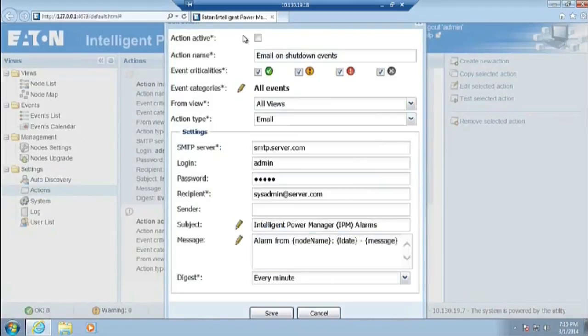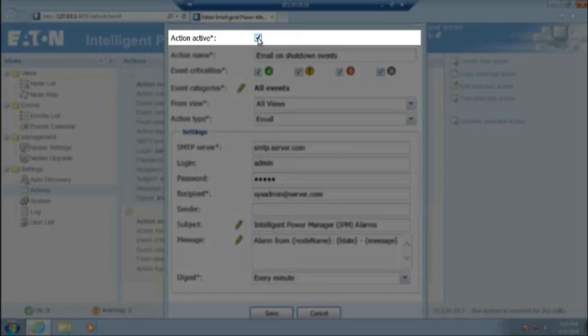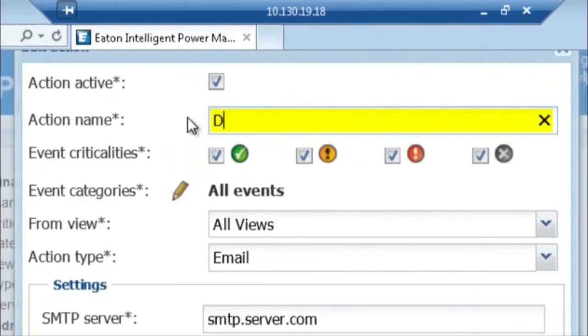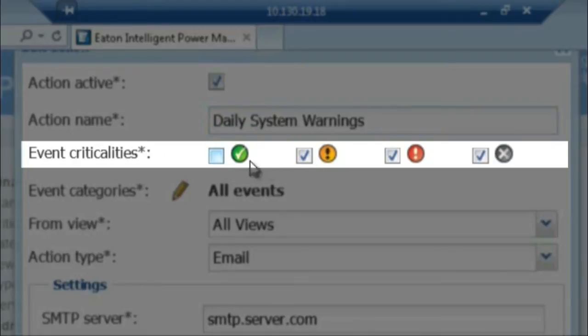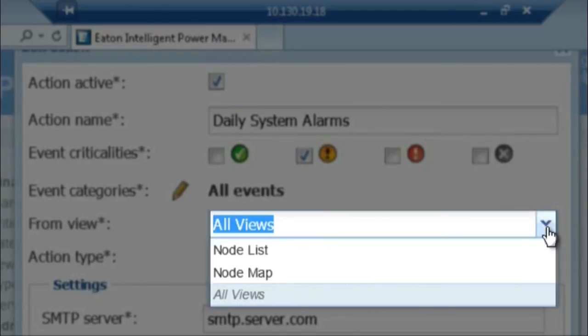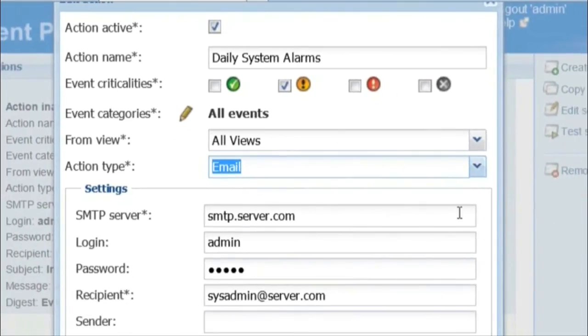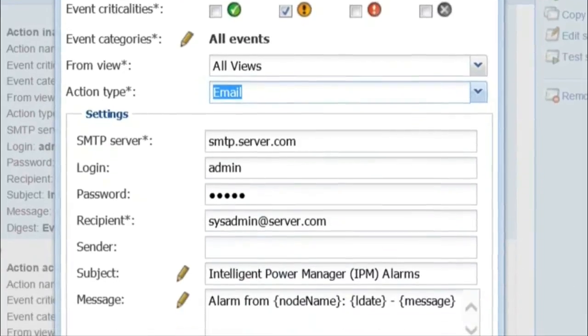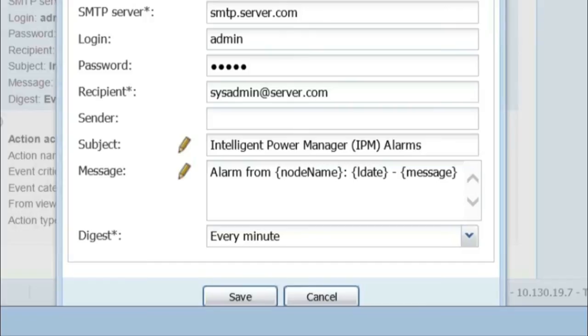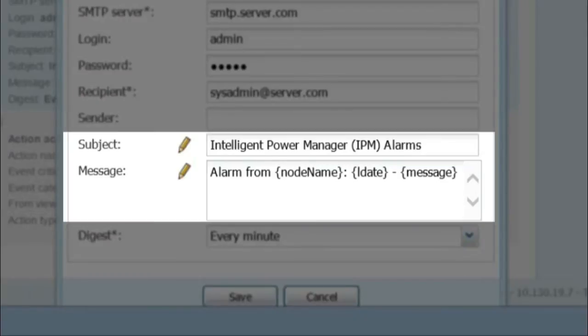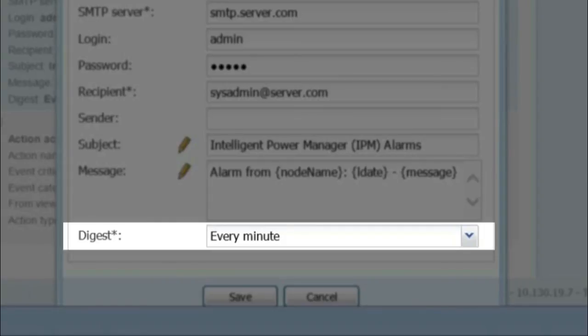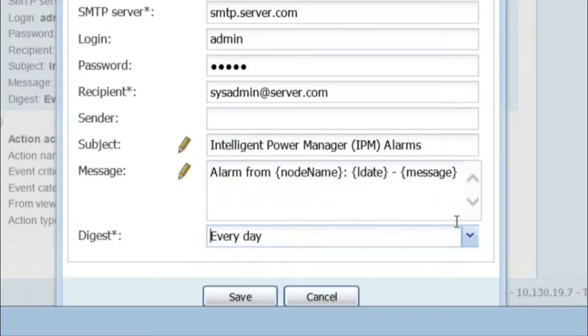Next, we will set up the criteria for email notification. Action Active: click the box on the right to place a check mark. Action Name: create a name for the specific action — for example, Daily System Warnings. Event Criticalities: only select the yellow exclamation icon box. From View: select all views in order to encompass all areas for alerts. Action Type: select Email. Define the SMTP server by entering the server information. Enter the login and password information. Recipient: enter the name of the person that will receive the email. The email subject and message will be populated based on the device that triggers the alarm. Set Digest to Every Day. Click Save to continue.